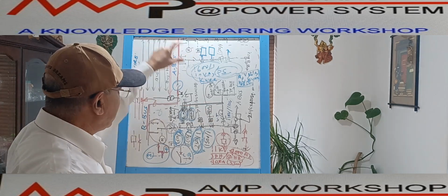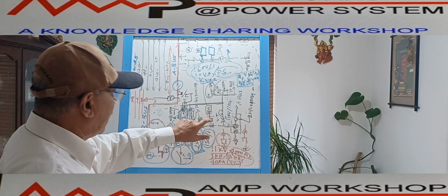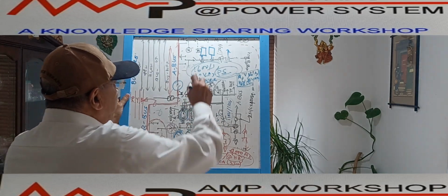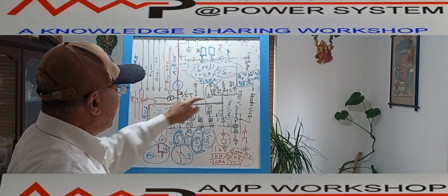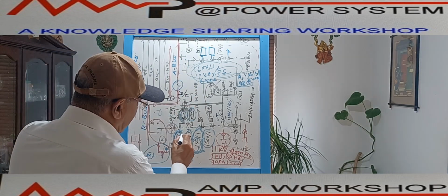Now for this total generator, I need only one PT, that PT over here. This PT supply also needs to go to the A bus. So from here also we can take the PT supply to the A bus. For the A bus, same arrangement. For the A bus also we have identical equipment. The same CT is there, this is for the relay. This is the A bus. You see, this is the A bus. For the A bus, this is a single line.